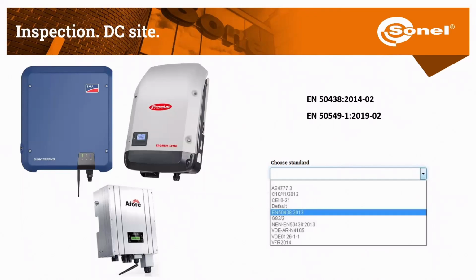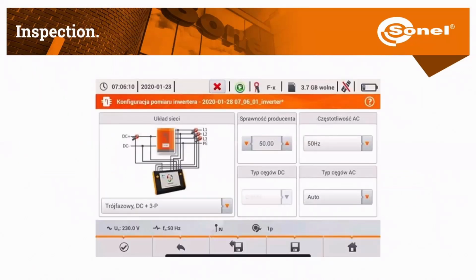This is also the test of the inverters. We have, for example, the power quality analyzer PQM 707, where the user can check the efficiency of the inverter, check the power and other parameters according to the standards. This is the print screen showing how easy it is to connect the PQM to the inverter and measure its efficiency, checking the DC side and AC side at the same time.